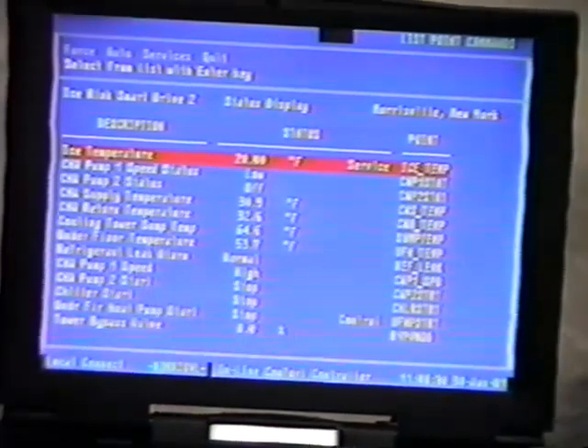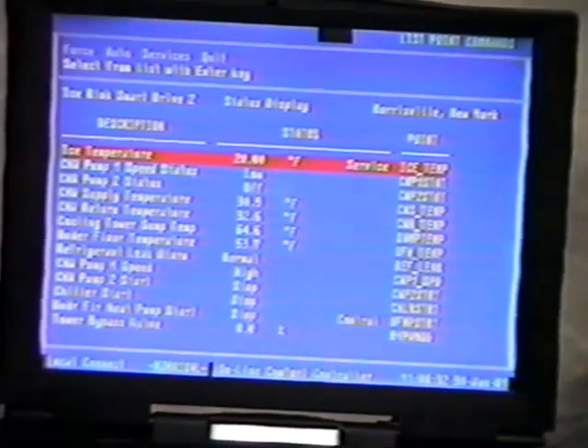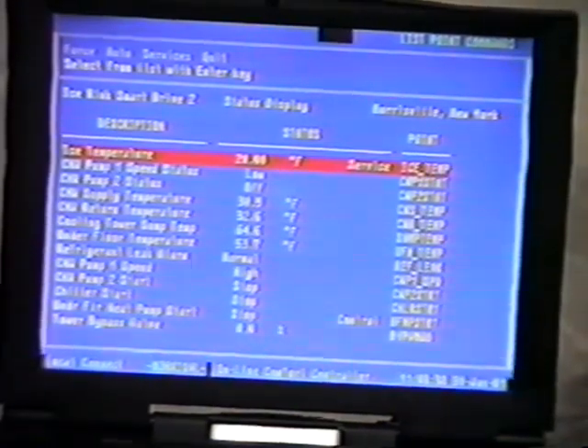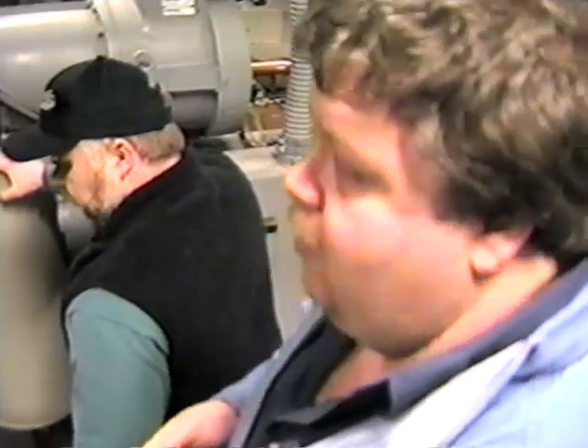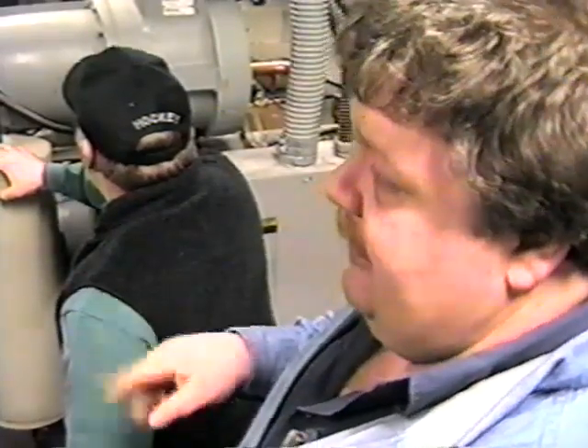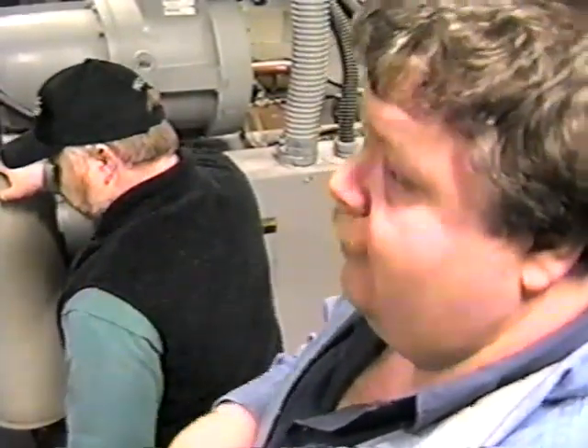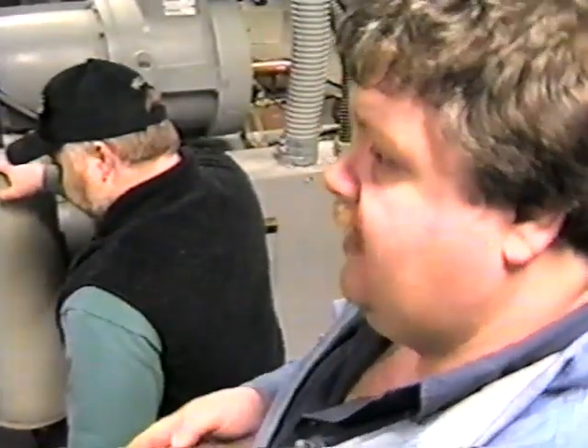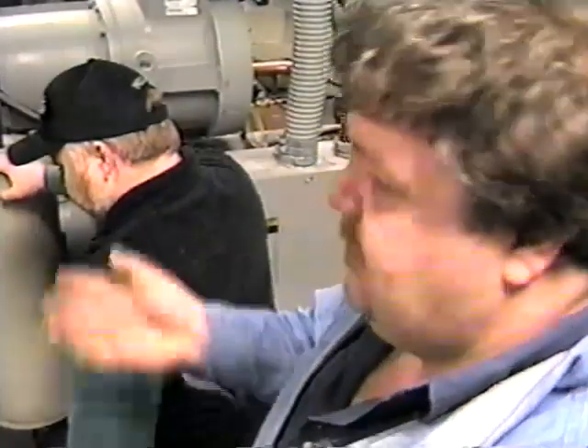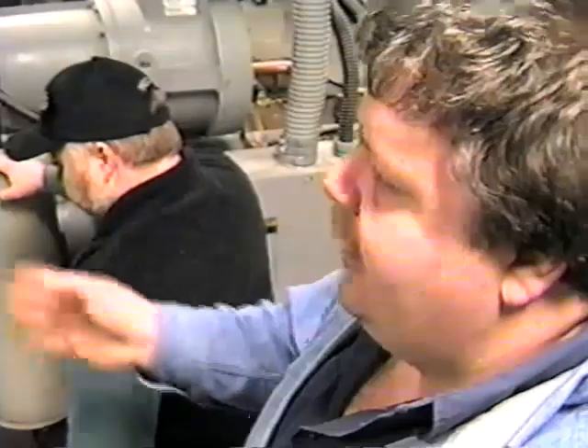When you're in high speed pump, which is predominantly what most ice rinks run, you're using, for an example, let's say $2.50 an hour worth of electricity to run the pump for like a 30 horsepower pump. By getting this to switch down to its low speed, we can get that down to about $1 an hour. And so over the course of the day, if we can keep this thing in low speed for a third of the day, we can save about $12 a day. So it adds up pretty quickly here.